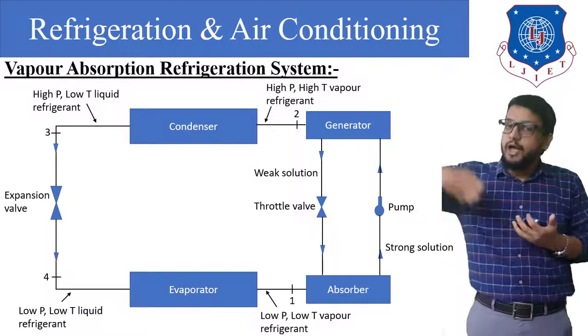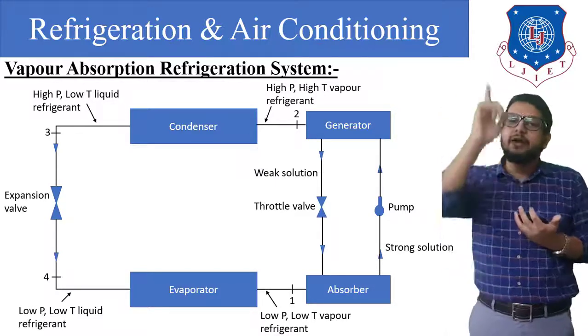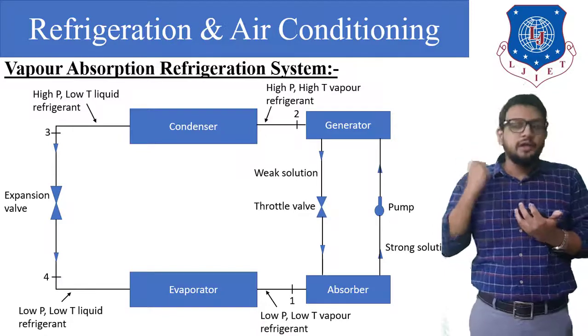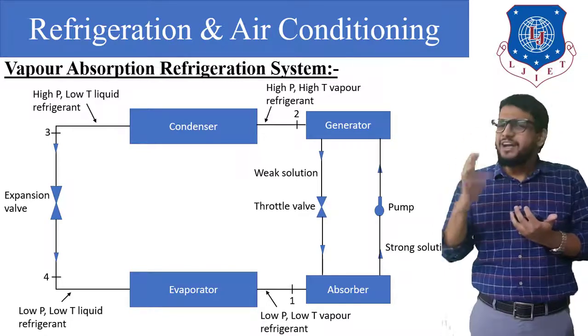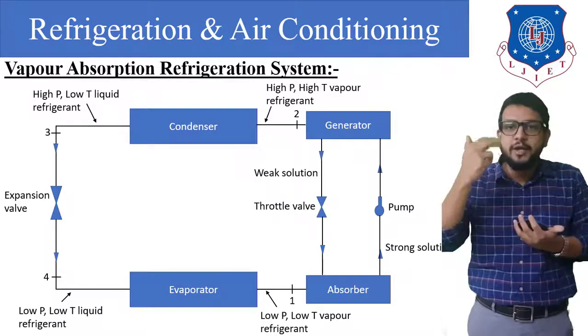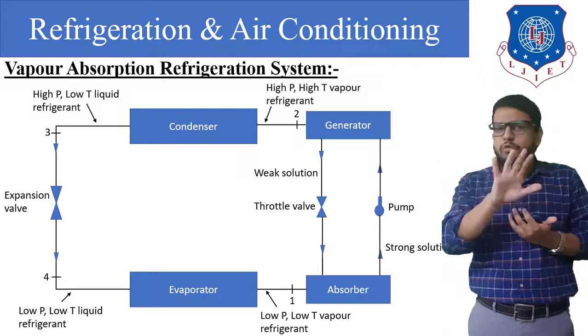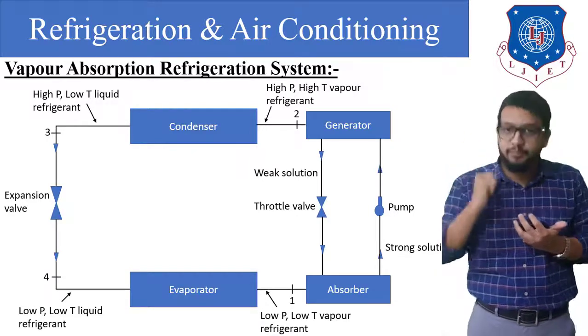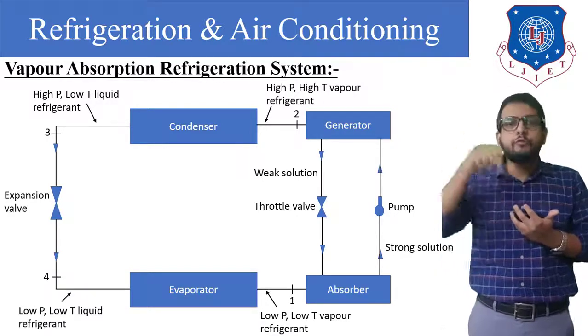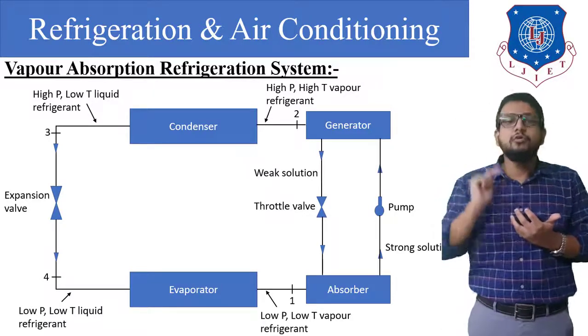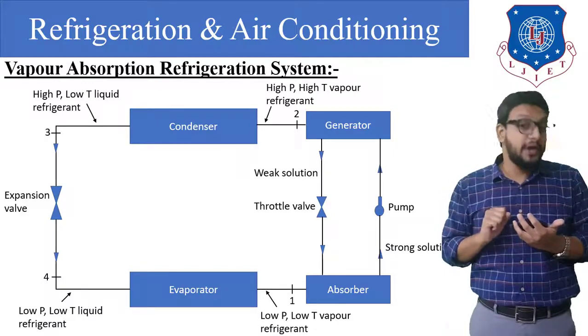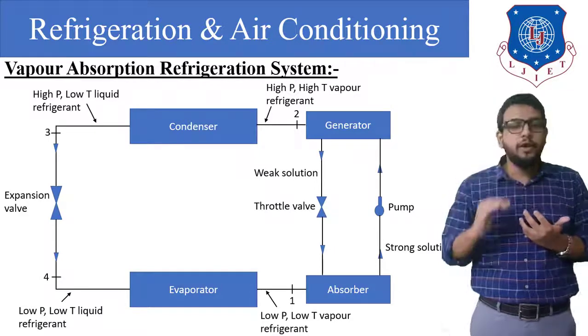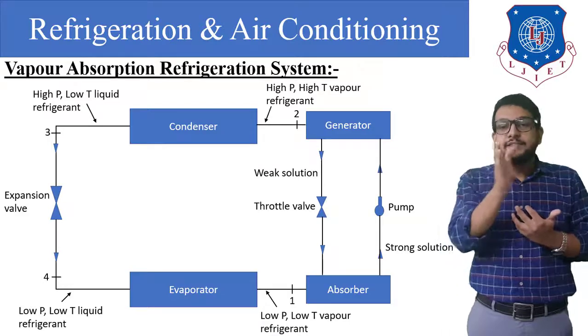The pump increases the pressure and supplies the strong solution to the generator. Once inside the generator, heat energy is supplied, solubility reduces, and almost 88% of the ammonia gets separated. The remaining solution — with only about 10–12% ammonia — is now a weak solution. That weak solution falls back into the absorber, but first its pressure must be reduced by the throttle valve before it re-enters the absorber.